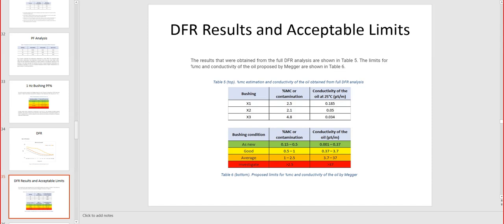DFR results and acceptable limits. Here we got basically conductivity and Megger values in percentage that indicate contamination. So recommended values. The results were obtained from the full DFR analysis shown in table 5. The limits for the percentage moisture content and conductivity of the oil proposed by Megger are in table 6.